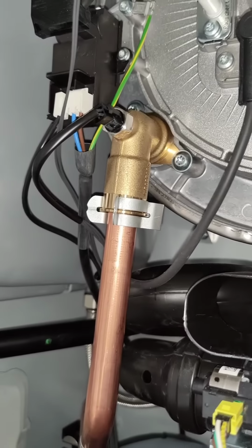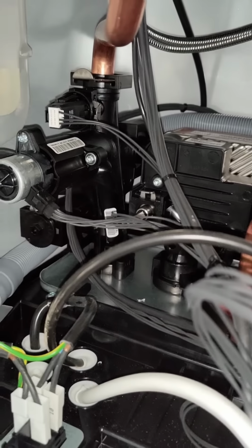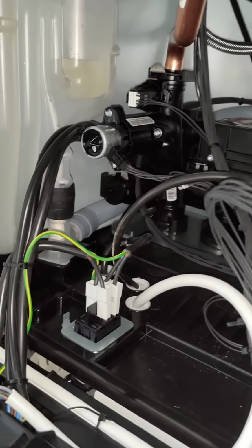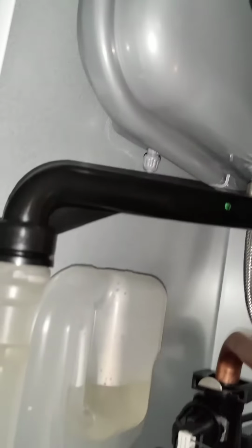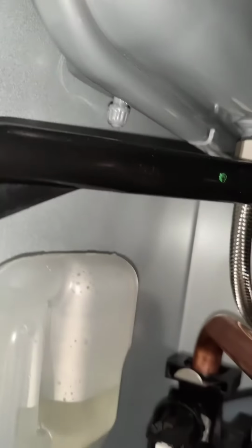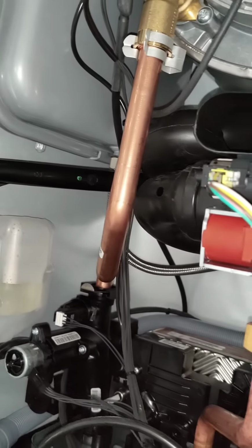You've got copper tubes coming from the heat exchanger, and with some of the older models there's rubber tubes that used to get blocked up. We have got quite a lot of this composite plastic inside there, but I've heard that it doesn't leak, so it's maybe a good thing. Loads of room to work. Expansion vessel Schrader valve on the underneath of the vessel, easy to get to. Really sturdy front panel.